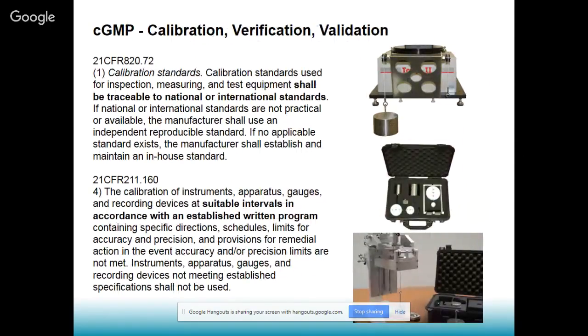As far as the CGMP calibration, verification, and validation concerns, I just wanted to point out 21 CFR 820 and 211 as far as the calibration related regulations. It should be noted that the weights should be traceable to a national standard, and it's critical from their perspective that you do the calibration at scheduled intervals, that there's a written calibration program at your facility, and that you record the calibrations, apply stickers on the machines, and have calibration records available in your documentation system. Because this could be another major reason why products could be recalled.